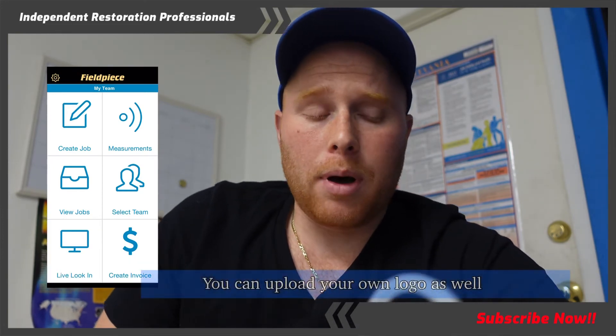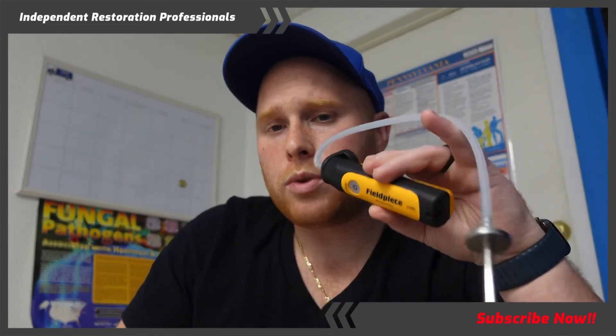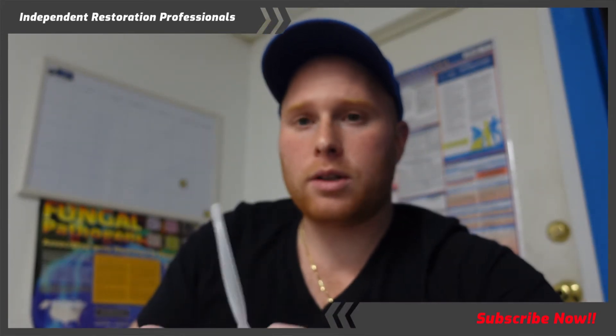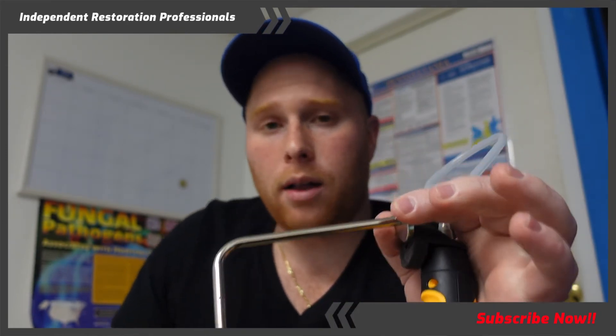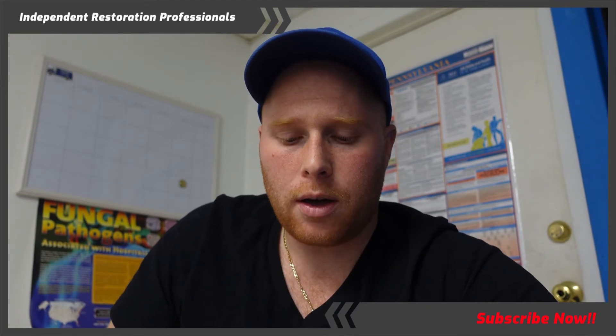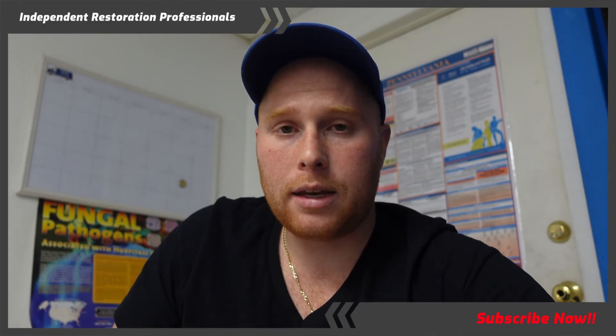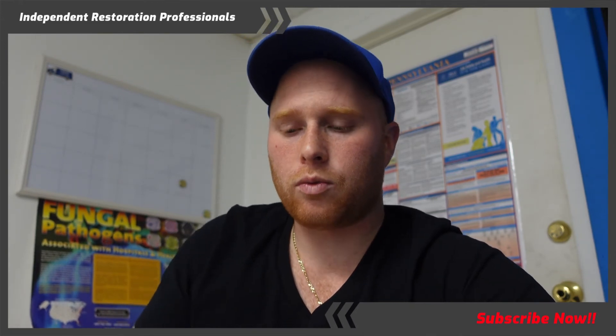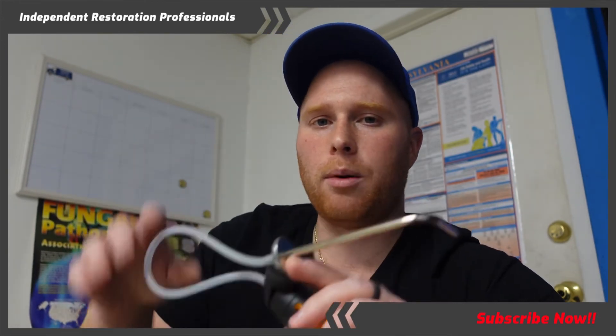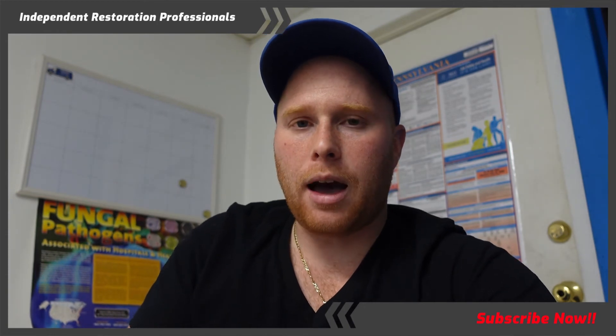Keep in mind I've used these on two or three jobs, so I have limited experience. What I found is that they work really, really well for indoor/outdoor containment — they show you the pressure differential. You can set goals and do what you need with that information. It's really handy; you don't have to run any cords anywhere, you just set it up wherever you need the reading.